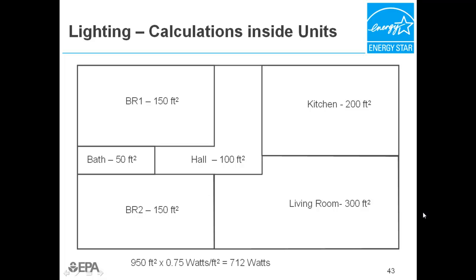Each room does not need to meet the 0.75 watts per square foot requirement, as long as the overall lighting power density does not exceed it. The prescriptive requirement can be used as a guideline for selecting fixtures. For example, a 50 square foot bathroom should target about 37 watts to maintain that lighting power density.